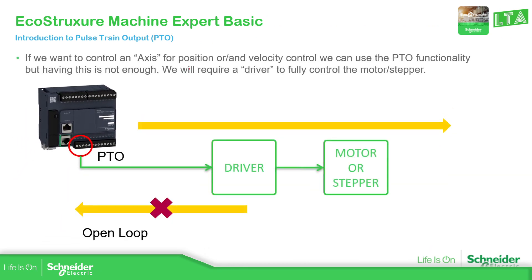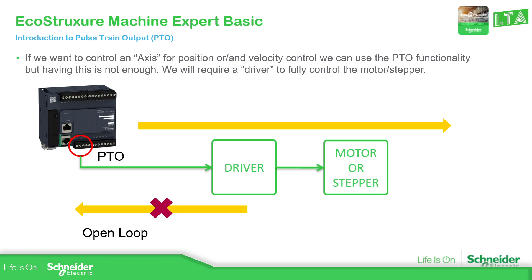Knowing that, what we need in order to control a motor or a stepper is a driver. We cannot directly connect the PTO outputs directly to the motor or stepper. When we connect the output of the controller, it just controls the driver, but we don't have any feedback — so this is an open loop. For example, if we want to know the exact position, we can use an encoder connected to the pulse input of the PLC.